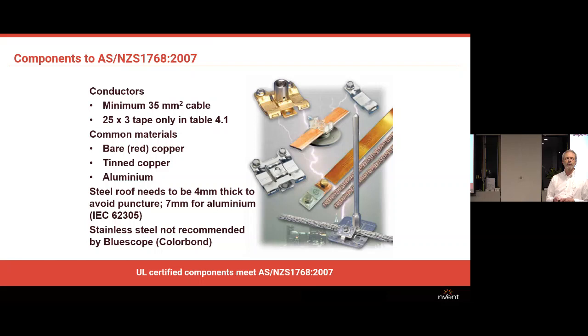If you can get away without using any of these components, the structure can be self-protecting. If you're happy that a lightning strike that melts metal is not going to put a hole in your roof, or if it does, it doesn't matter if your roof leaks. The wording underneath that list says that steel roofs need to be 4 millimeters thick to avoid puncture and 7 millimeters for aluminium. That comes from the IEC 62305 standard because the New Zealand standard isn't quite so specific about that.